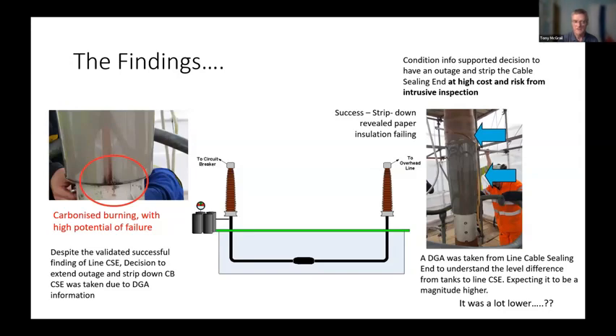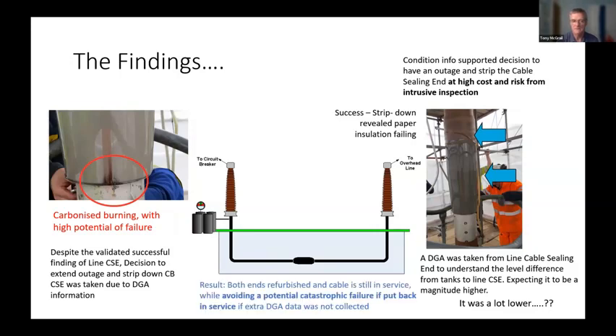Taking the cable sealing end apart, we found burning, high potential of failure, all sorts of issues that were then addressed by fixing that and would not have been if we hadn't done that DGA sample, and we would expose people to a far higher likelihood of a cable failing on a substation with man. Next one, please. Catastrophic failure avoided. Okay, one more.